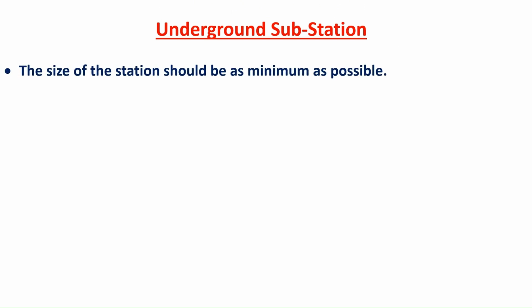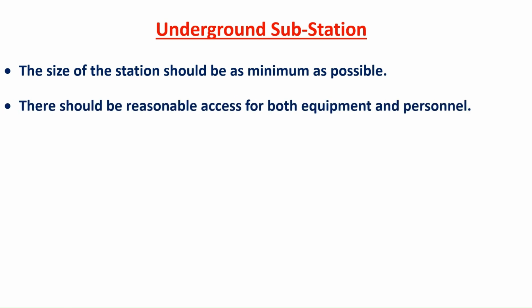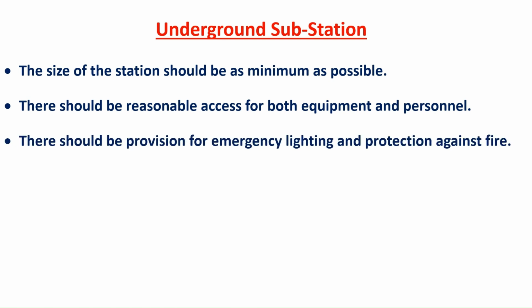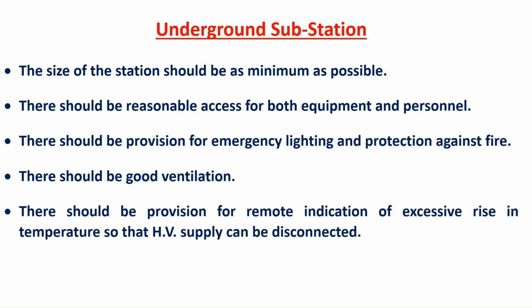While laying out an underground substation, a few points must be considered. The size of the substation should be as minimum as possible. There should be reasonable access for both equipment and persons. There should be provision for emergency lighting and protection against fire. There should be good ventilation. And there should be provision for remote indication of excessive rise in temperature so that the high voltage supply can be disconnected.